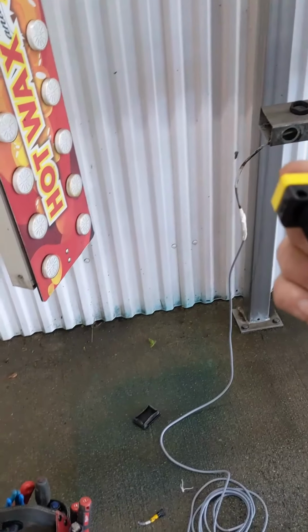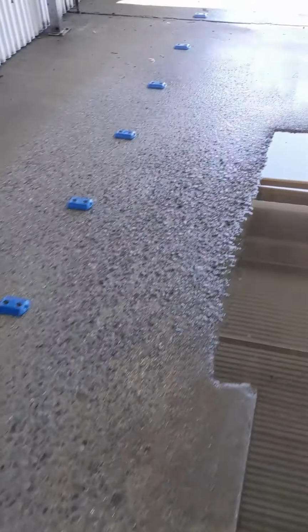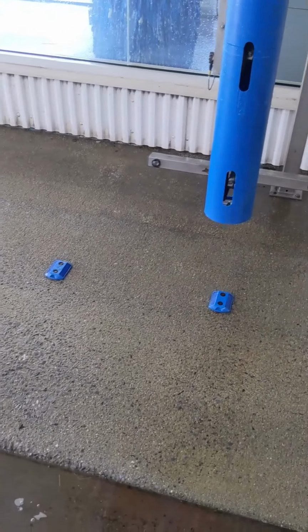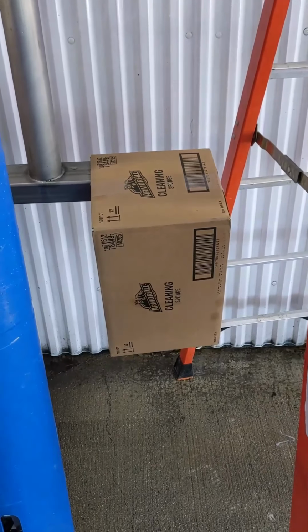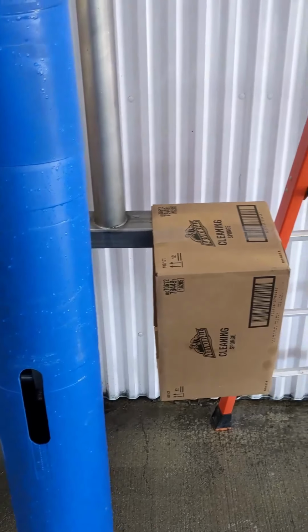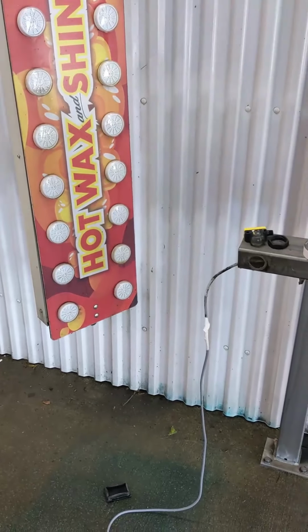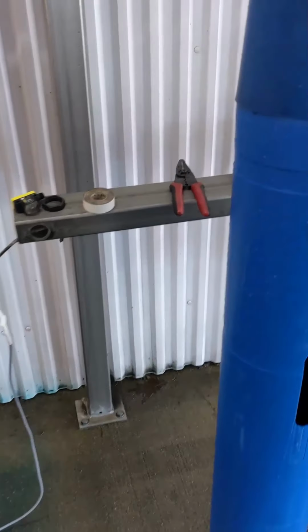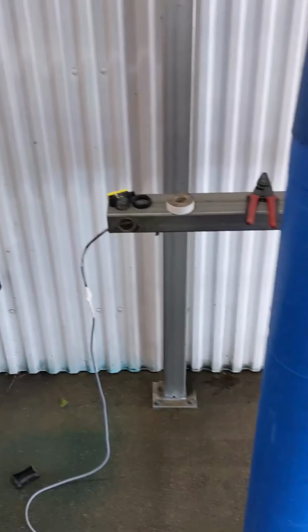Okay, so if you have it blocked, say you're standing in front of it, what I usually do is I take a box, and I'll show you this again once I turn the power back on. But I'll take a box and I'll just put it over the eye. All right, so now it can't possibly see the other side. So if you put the box over it and it stays on, then you know that it's either the receiver or the cable, all right? And then you just have to go through and see if you unplug it, if it stays on.